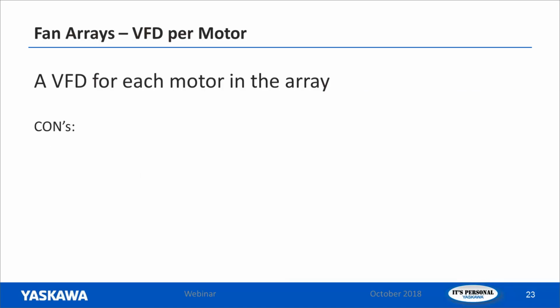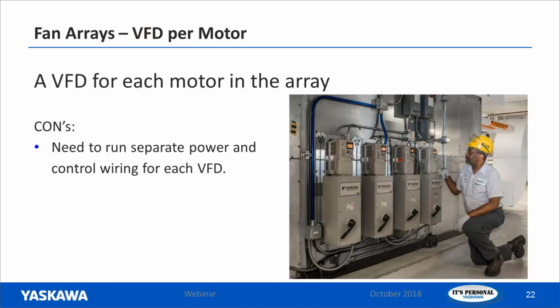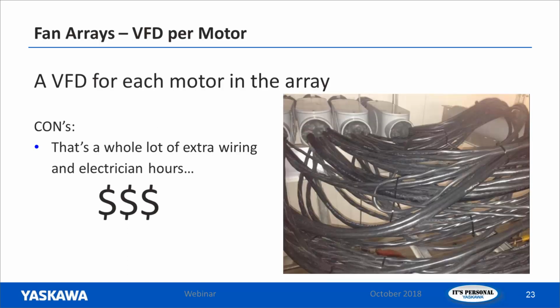It could get messy. Especially with the output. I mean, you're running separate input power to each VFD, but the output power definitely has to be separated. If you're using multiple VFDs in an array, each one has to have its own output conduit run to the motor that it's running. They cannot share output conduit. Whereas if you do it with one VFD, those motors can all share the same conduit from the output of the drive to the motors. And of course, the more wiring you've got to have, the messier it could get, putting money in for electrician hours and whatnot.